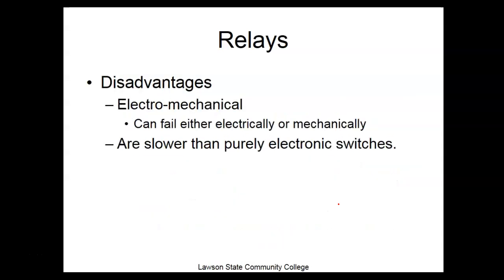The only disadvantage we have with relays is they're electromechanical devices, so they can fail electrically or they can fail mechanically. My son just brought his control board for his dryer over to the house. It wouldn't work, and when he opened it up and tapped on the relay, it would work. So he bought the relay. The board was going to cost like $240, and the relay cost like $8. He brought the circuit board over to the house, and I put it on there for him, so it cost him $8 to get that fixed.